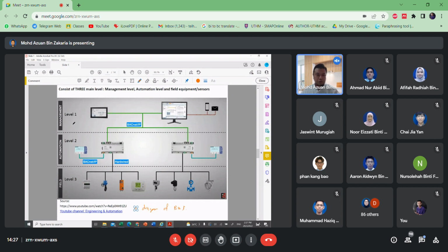So how to show the diagram? You need to show these three levels. Let's go to number three first. Level three is the equipment, sensors or equipment on site, on location. For example, air conditioner part, lighting, and maybe fire protection. So at the field level, these are all the services installed, and all these field sensors will be connected to the controller.